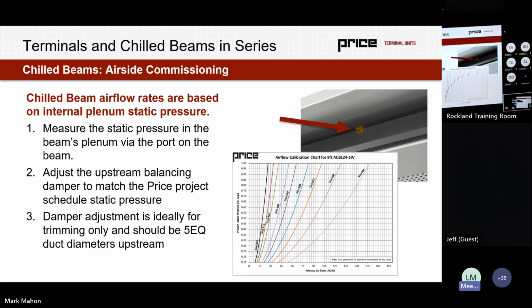So looking at the way we actually commission these really quickly, we measure the static pressure in the beam's plenum via the port in the beam. We adjust the upstream balancing damper to match the actual pressure that we need. So that could be the Price project schedule, which would come from the beam calculator, which Chris is going to look at for us shortly. Or that could be a static pressure off of engineering documentation as well, or out of the IOM, which is what I have on screen here.